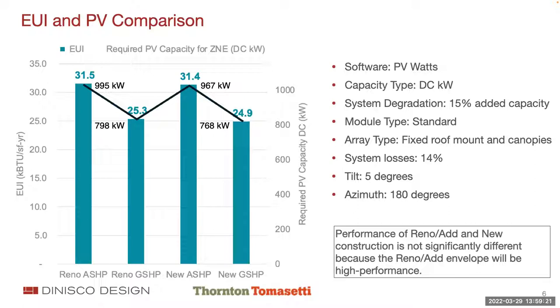So I go across to the center, to the air source heat pump column, and that EUI rises from 24.9 to 31.4. It's the same building. The only difference, as I understand it, is that there is an air source heat pump heating and cooling system, not a ground source. So we attribute the difference of 6.4 or so of the EUI to the air-sourced heat pump over the ground-sourced heat pump.